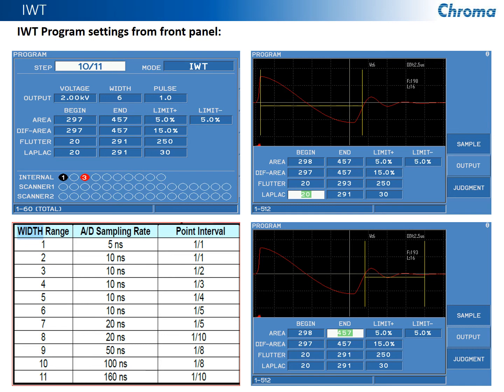Again, down here shows the scanner, the channels on the internal scanner on the 19036, as well as two additional scanners, and you can select between any of these different channels to use for your test points for your device under test. The nice thing about it is the sample that you see here in red for your known good sample will be stored, and all subsequent tests for any like device would be compared against this. So we normally do a sampling of a batch of units and determine what is a known good unit to use as our sample. But if you need more detail on this, please let us know. We'd be happy to go into a lot more detail about impulse winding testing.